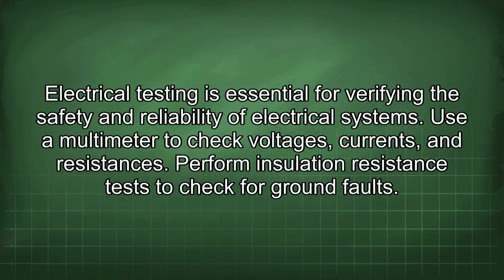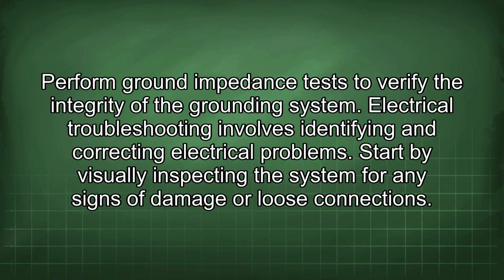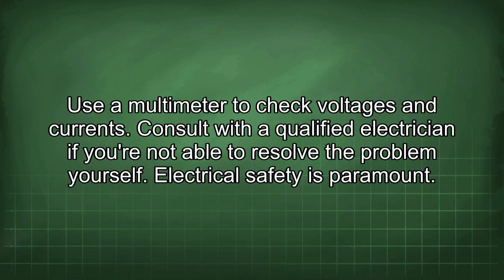Electrical testing is essential for verifying the safety and reliability of electrical systems. Use a multimeter to check voltages, currents, and resistances. Perform insulation resistance tests to check for ground faults. Perform ground impedance tests to verify the integrity of the grounding system. Electrical troubleshooting involves identifying and correcting electrical problems. Start by visually inspecting the system for any signs of damage or loose connections. Use a multimeter to check voltages and currents. Consult with a qualified electrician if you are not able to resolve the problem yourself.